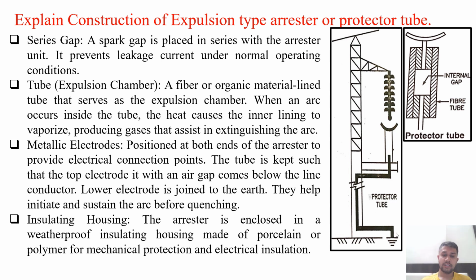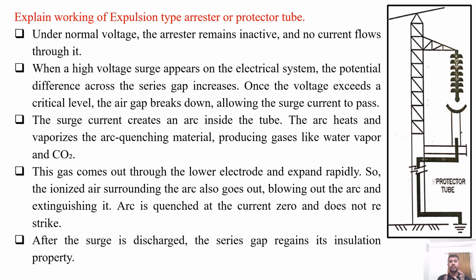Insulating housing. The arrestor is enclosed in a weatherproof insulating housing made of either porcelain or polymer for mechanical protection and electrical insulation. So these are some basic constructional details of the expulsion type arrestor or protector tube. Explain the working of the expulsion type arrestor or protector tube type arrestor.